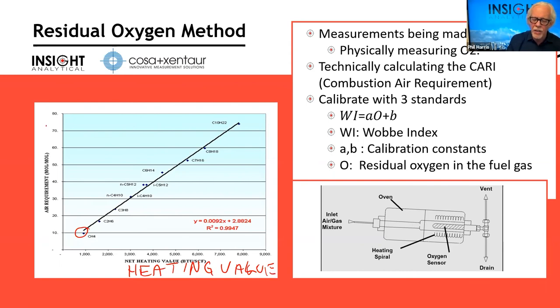This is air requirement, or air required. So what it tells us is that if we know this thing is somewhere between 1 carbon and 2 carbons as fuel, from that N and M thing, we know it's sitting right around here. It tells us what the net heating value is. It looks like about 1300 BTU, and it says it needs about 13 units of air for every mole of hydrocarbon I'm going to put in the burner. So now if I'm measuring my flow rate into the burner, I know how much air to add. Whatever flow rate of fuel is going in, I add 13 times that much air.